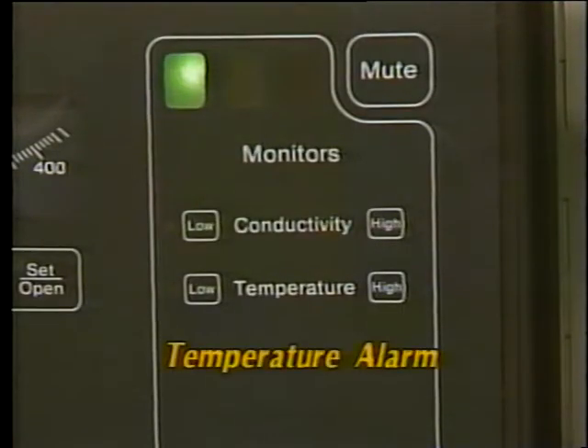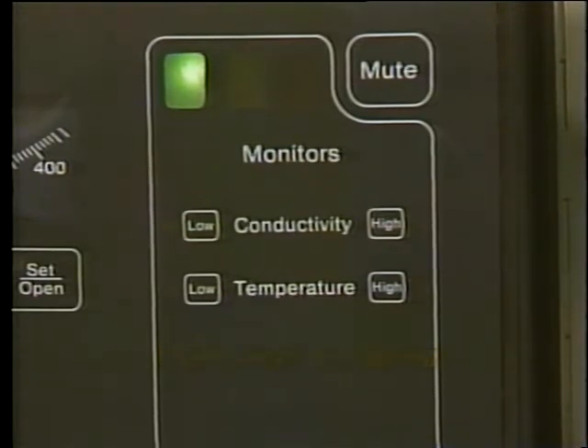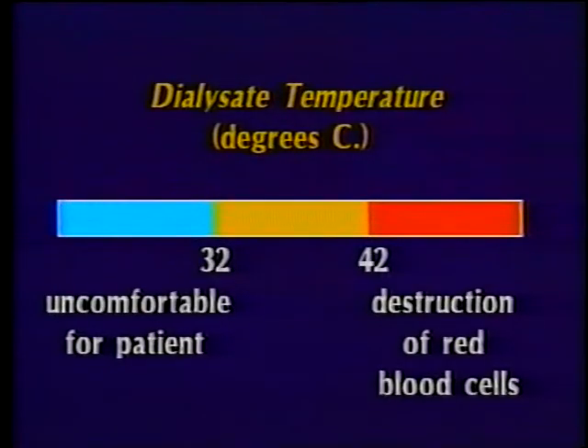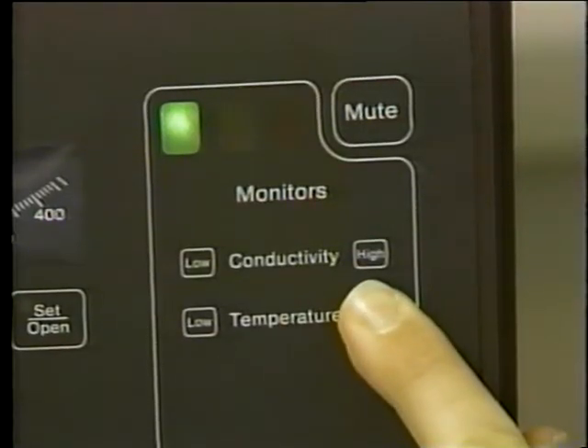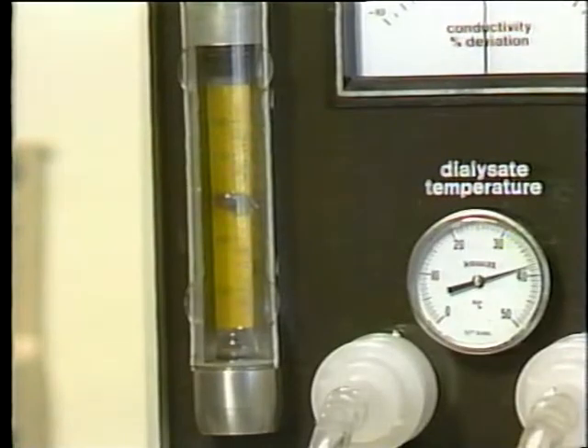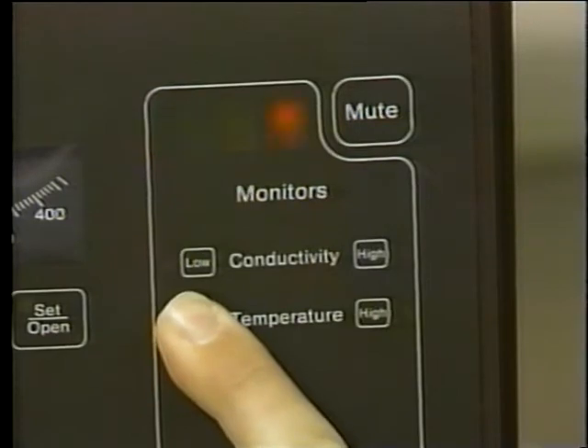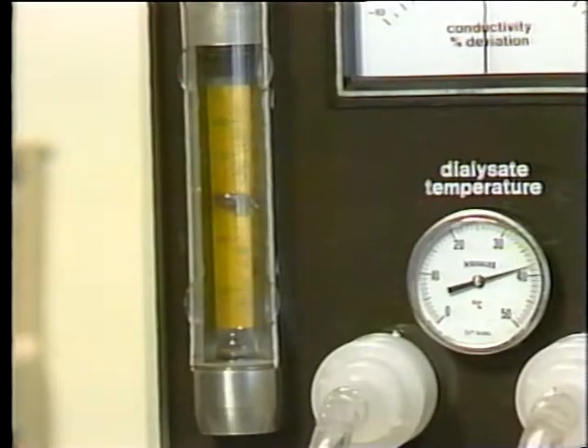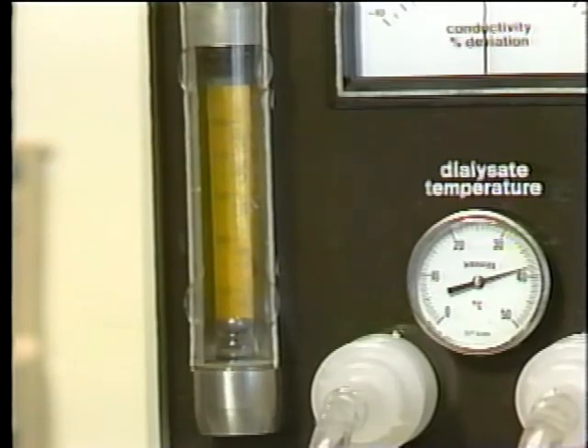For example, the temperature monitor must be checked before beginning dialysis. The dialysate must be at normal body temperature. Cool dialysate is not always harmful, just uncomfortable for the patient. However, dialysate over 42 degrees centigrade will cause destruction of the red blood cells. The patient will become symptomatic almost immediately from a lack of oxygen. Test the temperature alarm by making sure the overheated dialysate bypasses the dialyzer. Some machines will also bypass in low temperature. Also, verify both audible and visual alarms.